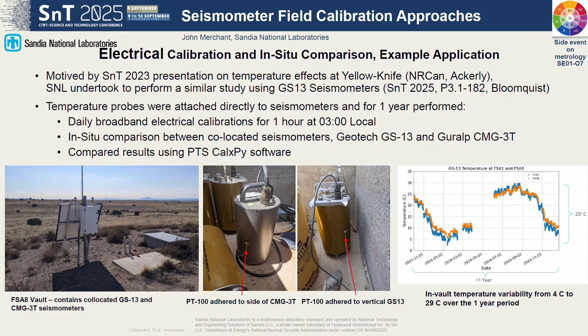And so we ended up with a fairly large data set of comparisons between the voltage signal into the calibrator and the output of the seismometer on those two instruments. And then we took the additional step of doing in situ comparisons between the measurements of ground motion between the GS13 and the CMG3T. We took advantage of this PTS CalXPy tool, which helps find time periods and frequency bands of coherence and assemble it into a usable representation of the response, and gave us some metrics of how much these parameters are varying over the 1 year, where we see this temperature variability of approximately 25 C at our facility over this year. And I should say that's 25 C on the seismometer case, not the outside.